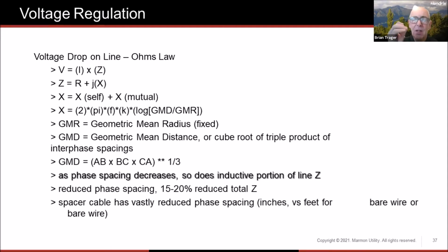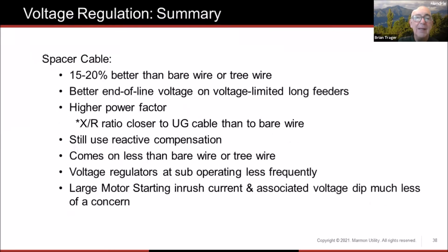So we're reducing the total impedance by 15 to 20%, which means I'm going to have 15 to 20% better voltage regulation than bare wire. I'm going to have a 15 to 20% better end of line voltage on voltage limited feeders, on any feeder. I'm going to have a higher power factor. So I'm going to have an X-on-R ratio closer to underground cable than to bare wire. I'm going to still use reactive compensation cap banks, but they're going to come on less than bare wire or tree wire. And the voltage regulators at the sub are going to be operating less frequently.